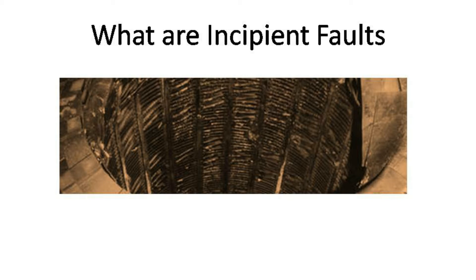What is really tricky about these incipient faults is that, even though they may cause things like shorting of a specific number of turns within the windings, these short circuits being created are actually relatively small, so there would not be a great change detectable when measuring from the terminal side of the transformer.